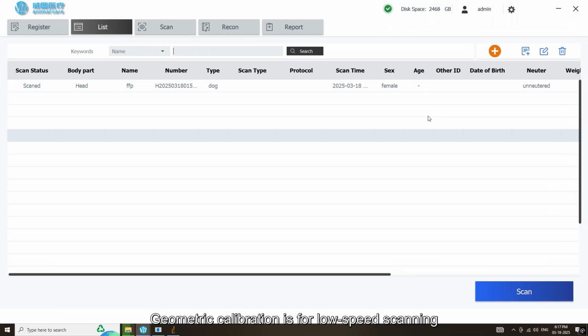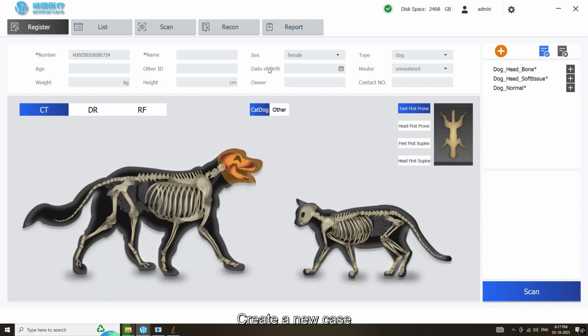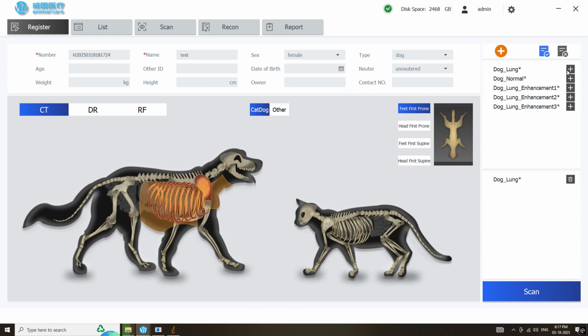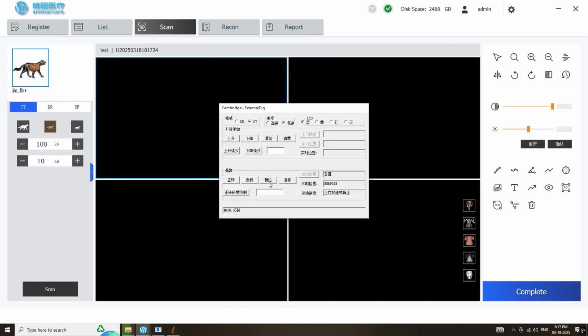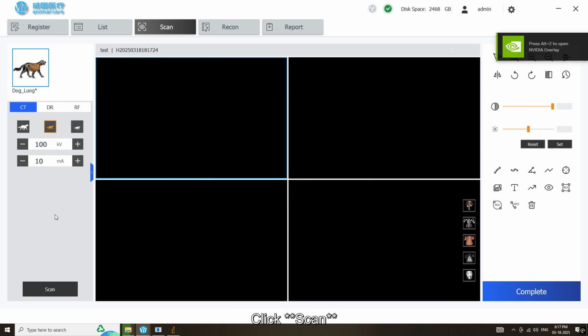13. High-speed image calibration 1. Geometric calibration is for low-speed scanning. Now, high-speed scan calibration needs to be performed. Create a new case. Select the lung. Check the rack position. Reset and clear to 0. Click Scan. Observe the image and make calibrations.